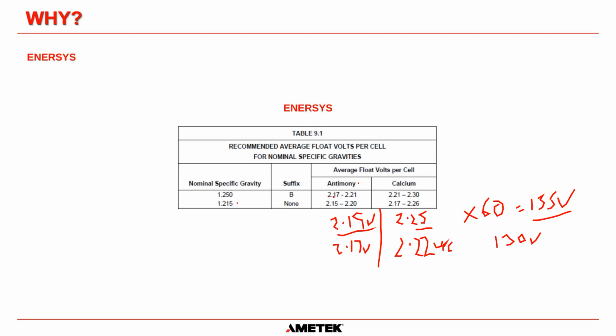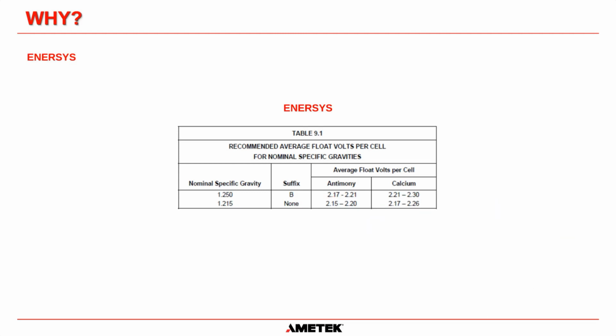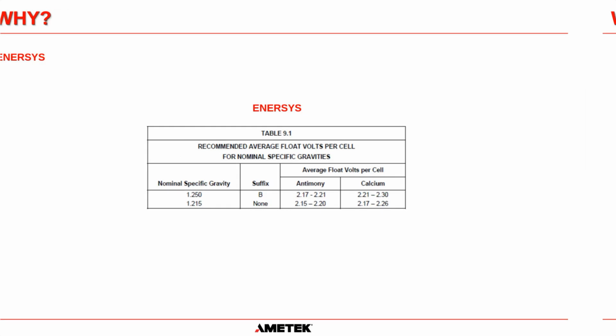60 times 2.19 is actually 131.4. It's not that, it's 131.4. So you can see there's nearly a 4 volt difference between those two. So you have to be clear that you check the manufacturer's guidelines before you set the float voltage on your system. And that's just for EnerSys.